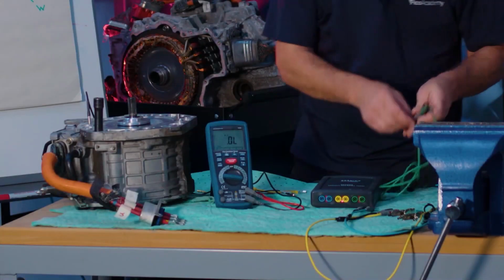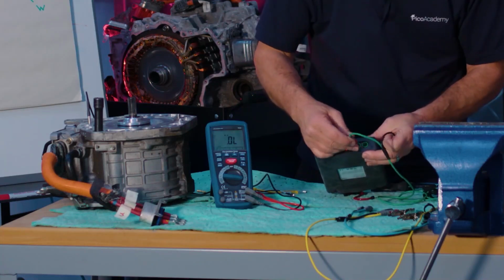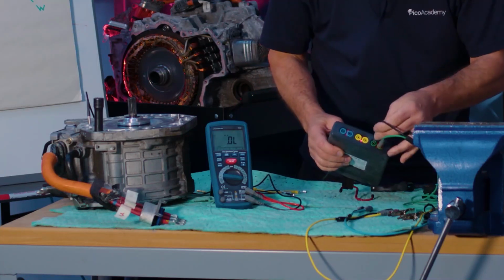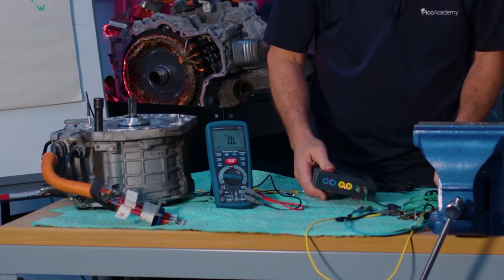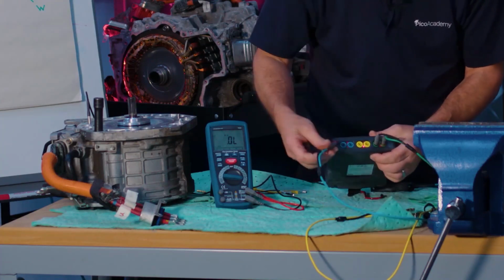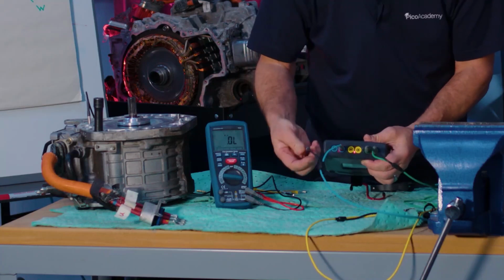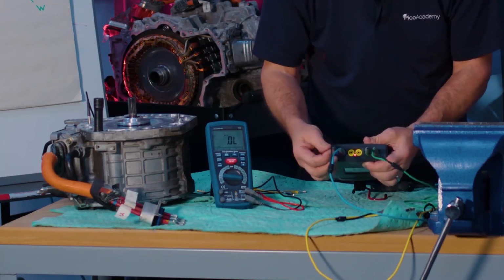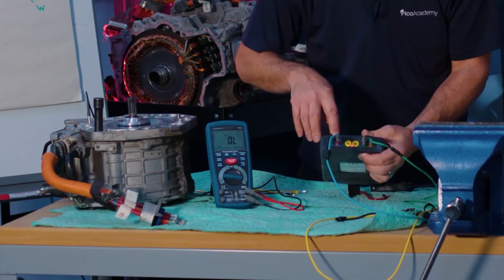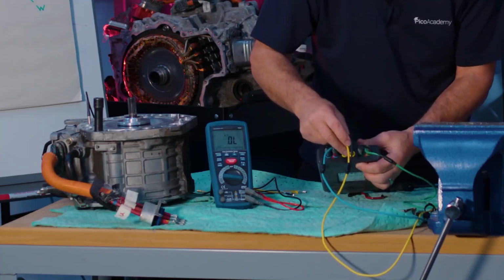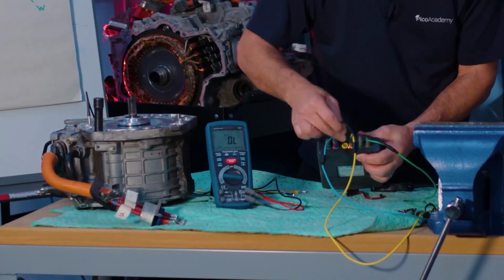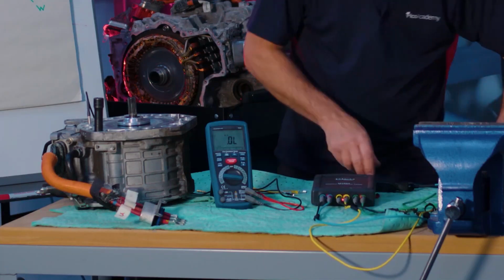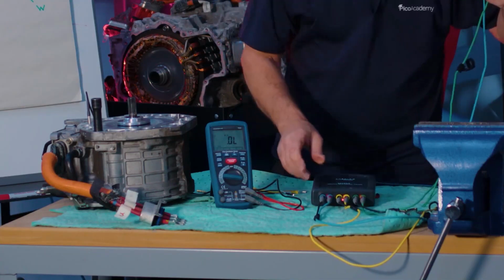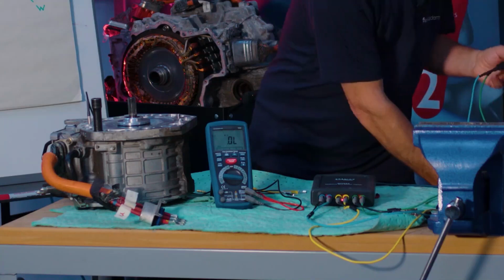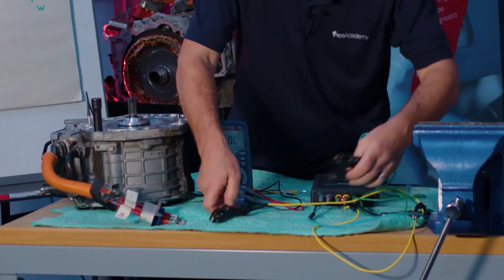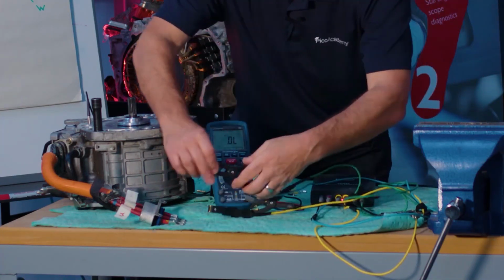The new Milliohm tester from Pico. You'll notice here that we have two leads. Remember, this is going to be a four wire measurement. We've got the red marker on the test lead to go into the red 4mm connection socket on the device, and we will connect exactly as it says there. So we'll have U, V and W as we've labeled up. U here is going to be blue.